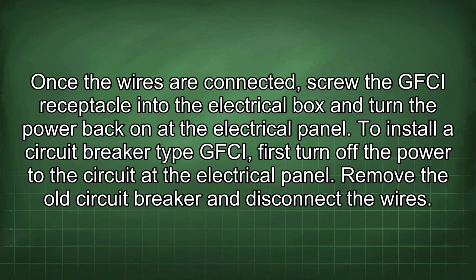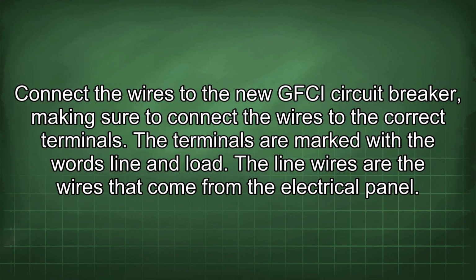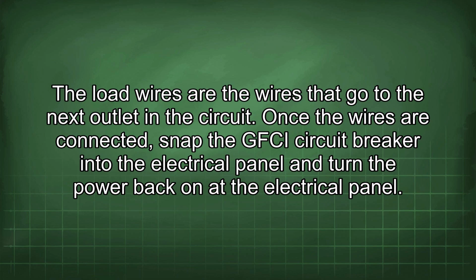To install a circuit breaker type GFCI, first turn off the power to the circuit at the electrical panel. Remove the old circuit breaker and disconnect the wires. Connect the wires to the new GFCI circuit breaker, making sure to connect the wires to the correct terminals. The terminals are marked with the words line and load. The line wires are the wires that come from the electrical panel. The load wires are the wires that go to the next outlet in the circuit. Once the wires are connected, snap the GFCI circuit breaker into the electrical panel and turn the power back on at the electrical panel.